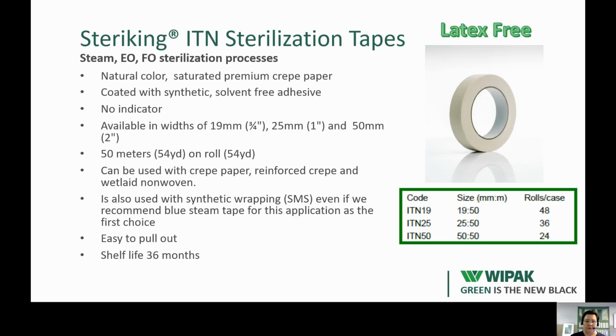First we have our neutral sterilization tapes called ITN. This is neutral in color, intended for steam, ethylene oxide and formaldehyde sterilization processes. It is made from saturated premium crepe paper. Crepe paper is normally used in these tapes to provide stretch so that the tape remains intact while the pack expands during the autoclaving process. Therefore the creping in these tapes is needed.